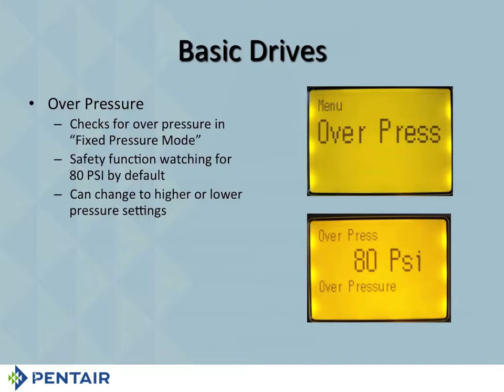He says 80. I said, all right, change that to 97. So he changed it to 97. I said, all right, now hit enter. So he hits enter. I said, all right, now go ahead and hit your status button and turn the pump back on. And it went right to 90 PSI. So the bottom line is that he hadn't changed his overpressure, but he was setting the pressure set point higher than what overpressure was. Going to hit overpressure, it's going to trip.